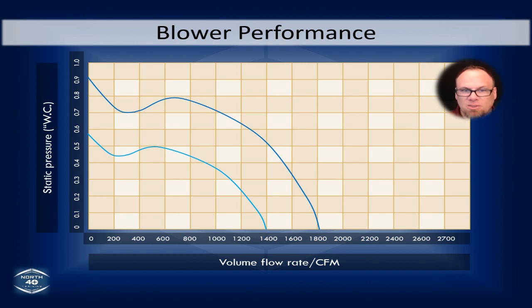Least amount of resistance, so we got 0 resistance, is the highest amount of airflow. So look at it this way. If we put a board, a piece of wood, in the filter box, it's going to catch 100% of all of the pet dander and allergens and dust mites and hair and everything you could think of. It's going to catch all of it. It's a 100% efficient filter. Now, how much airflow is moving through there? 0, right? So we got a 100% efficient filter, but 0 airflow is moving through there.